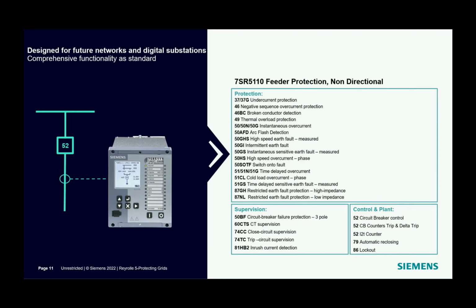It includes a core range of functions as standard. Again, I would like to emphasize this. Whatever functionality you see here on this table, those are all included as standard as far as the necessary hardware is chosen. Instantaneous and time-delayed overcurrent protection functions are 50 and 51. These protection functions provide three-phase overcurrent and calculated earth fault. Calculated earth fault is determined from the sum of the three-phase currents and uses the suffix n, as you see, 50n, after the function number.